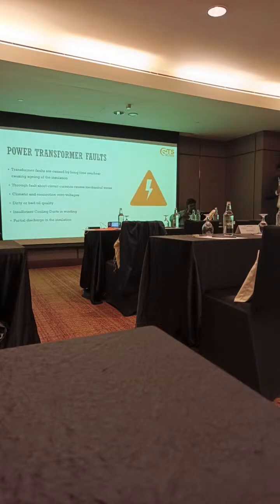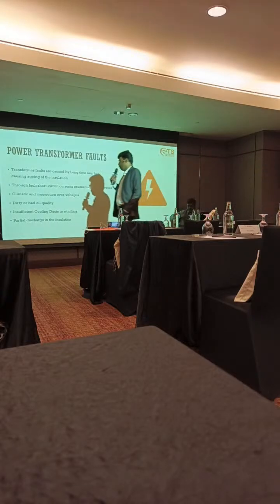Before going to the protection, we'll look into the types of faults that we might encounter in a transformer. First and foremost, a transformer fault can be caused by long-time overheating, causing aging of insulation, or many other factors. Overheating can be caused not only by aging, but also by short circuits, either in-zone or out-of-zone, both cases. Also, the transformer may overload for a prolonged time, and then overheating comes into the picture.